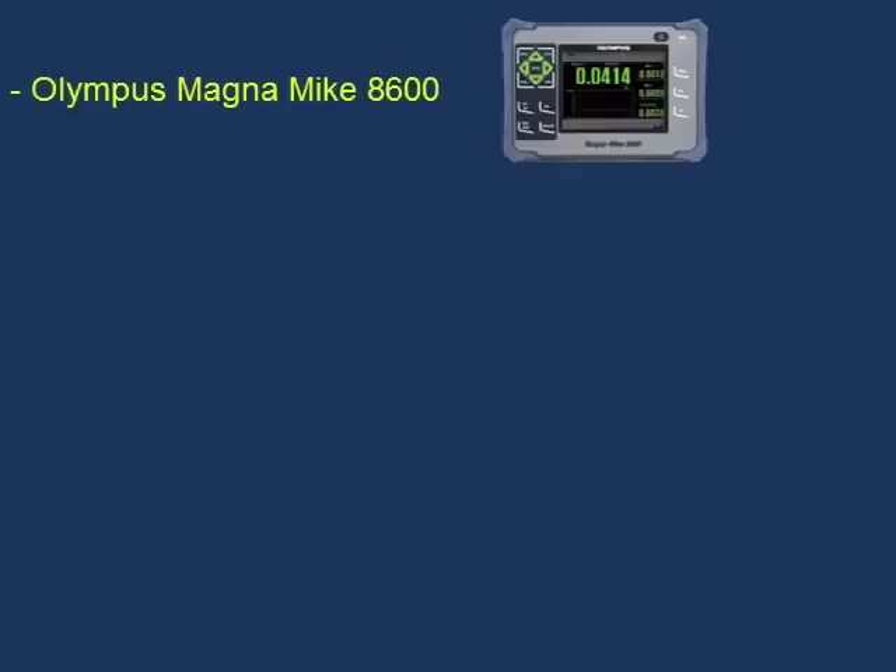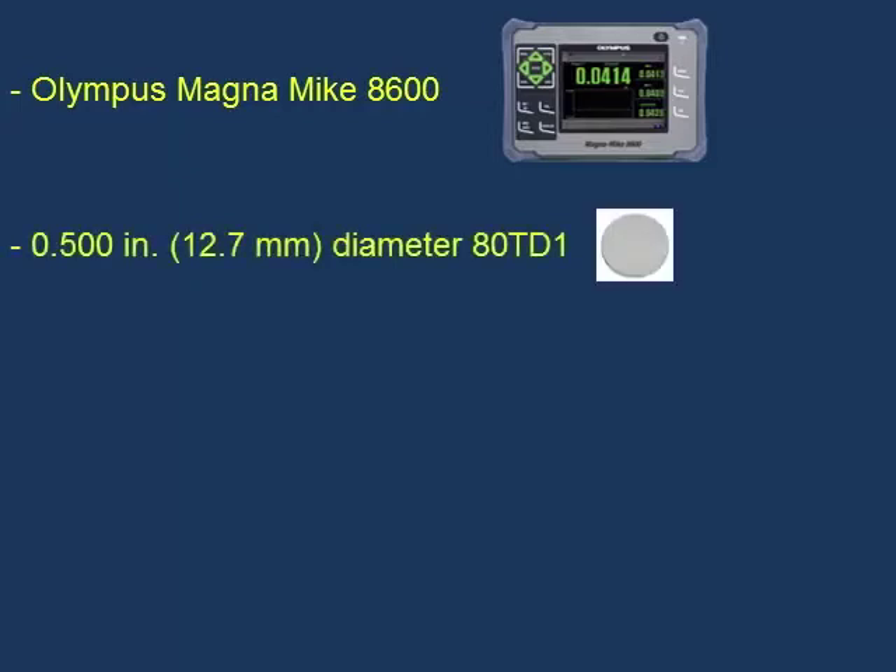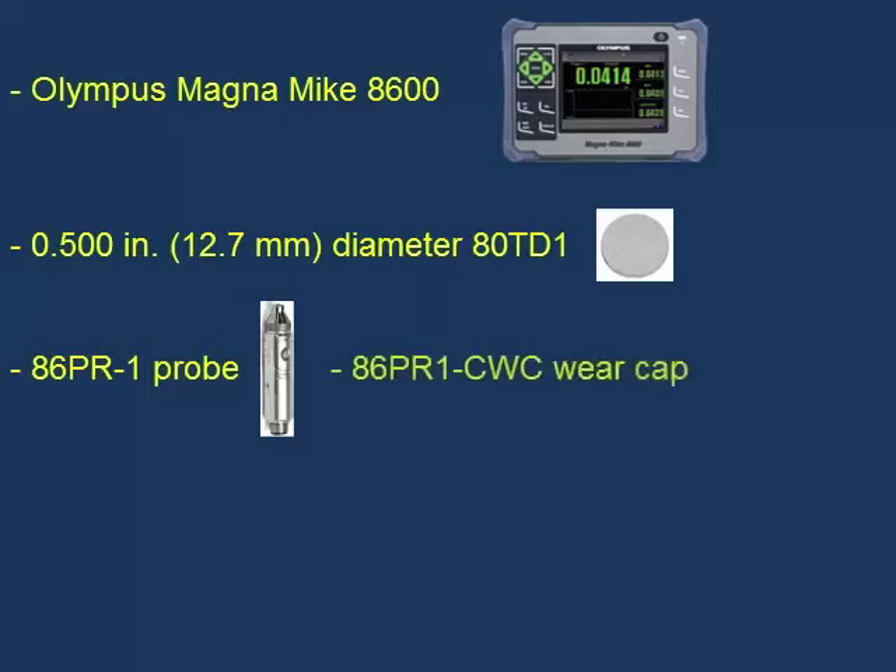In this demo, we will show how to calibrate the Olympus Magnamike 8600 using the half-inch or 12.7 millimeter diameter 80TD1 flat target disc. We will be using the 86PR-1 straight probe with the 86PR-1-CWC chisel tip wear cap and the 86PR-S1 probe stand.